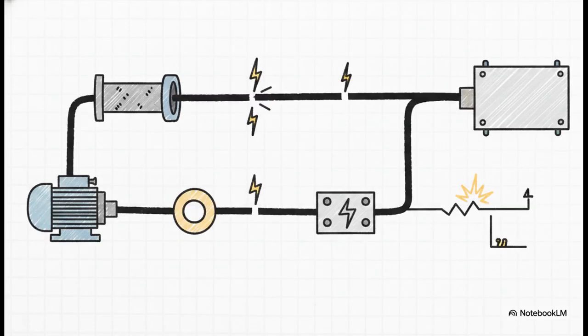So here's the deal with the concept of a certified system. In hazardous environments, the electrical wiring, the glands, the earthing, they are not just afterthoughts or accessories. They're integral, highly regulated components of the explosion-proof system. IEC standards and offshore regulations essentially say you cannot separate the equipment from its wiring. It's all treated as one continuous, certified chain. And you know how the saying goes, the weakest link is the one that'll cause a spark.